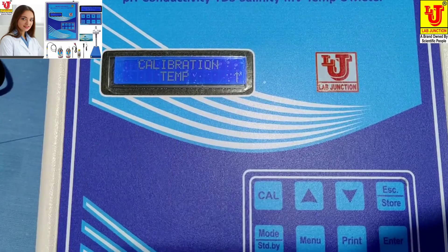Now I am calibrating pH. Now press the cal key. This is the temperature. I am calibrating pH, so go up. This is pH. Press enter. Buffer 1. Buffer 1 is 7 pH. Press enter. It shows 7.0. Press enter again. 7.00. And go up. Buffer 2. Buffer 2 is 4 pH. Press enter.